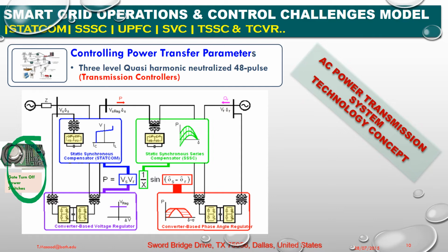These devices, referred to as turn-off devices, are more expensive and have higher losses than the thyristor without turn-off capability. However, the turn-off devices enable converter concepts that can have significant overall system cost and performance advantages. These advantages in principle result from the converters being self-commutating, as against line-commutated converters. Compared to the self-commutating converter, the line-commutated converter must have an AC source connected to the converter. It consumes reactive power and suffers from occasional commutation failure in the inverter mode of operation.